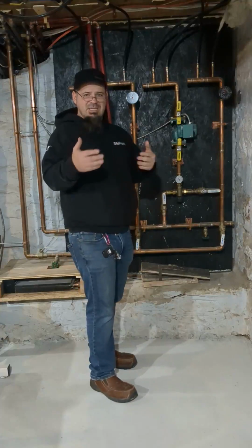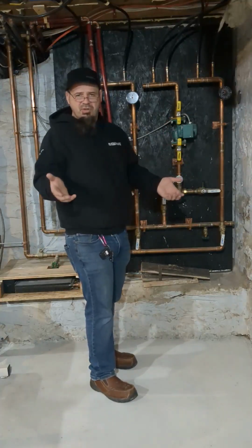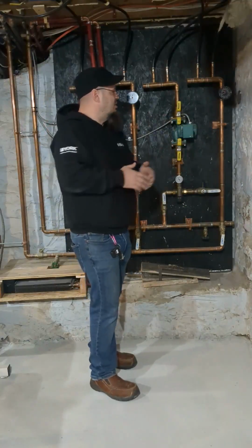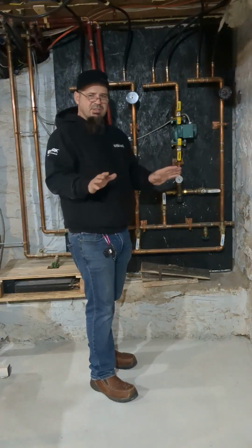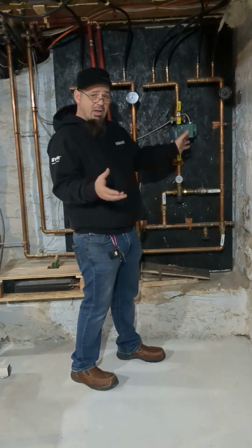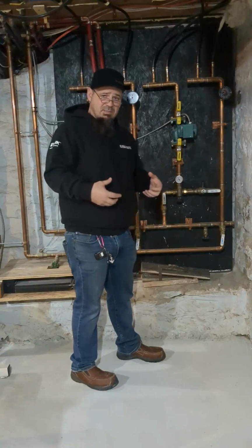And that gives us a design measure. The golden rule is we design for a 20-degree delta T. There are reasons to move that around once you become a designer, but that's pretty much the gold standard. Having both of these gauges lets me see where I'm falling in my delta T and gives me valuable input on what my system is doing.